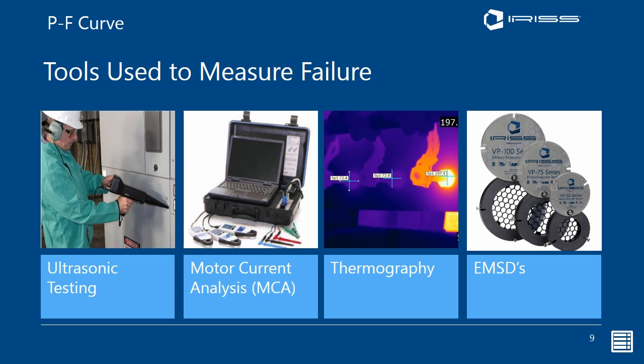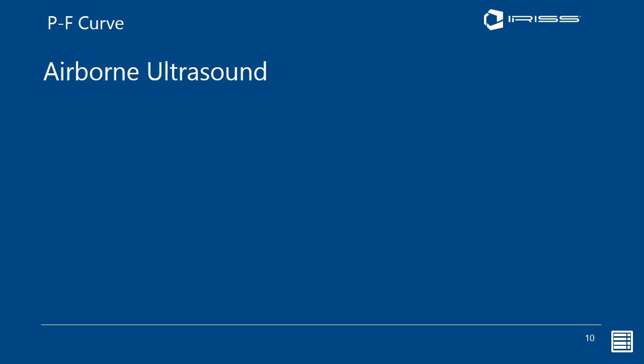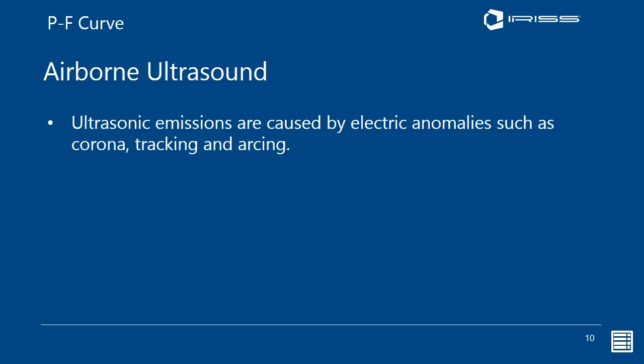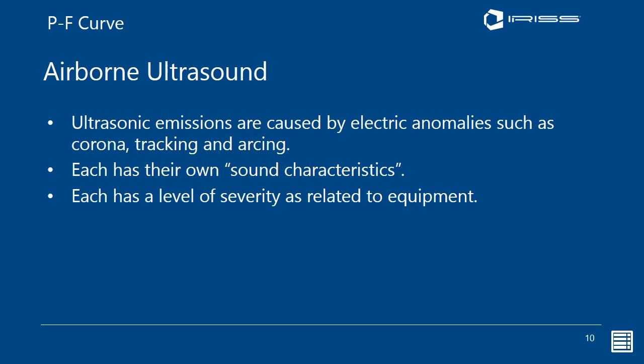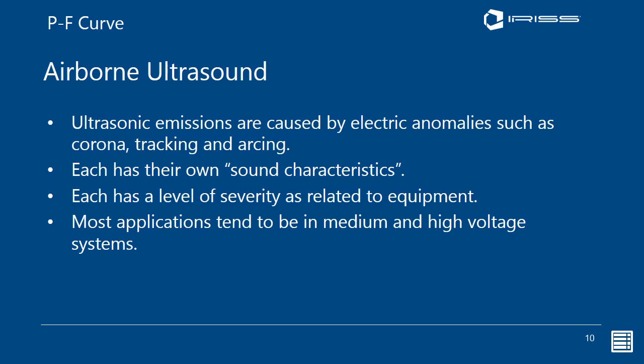First tool is airborne ultrasound. Ultrasonic emissions are caused by electric anomalies such as corona, tracking and arcing. Each has its own sound characteristic. Each has a level of severity as related to the equipment. And most applications tend to be in the medium and high voltage systems. The EMSDs used are ultrasound ports, and ultrasound ports are required for environmentally sealed panels, although some clients use ultrasound ports as a dedicated collection point for their ultrasonic equipment, so they get a standard means of collecting data and good repeatability on their trends.